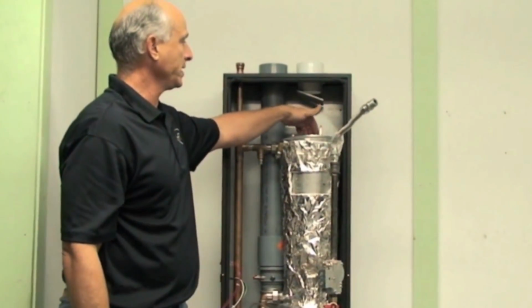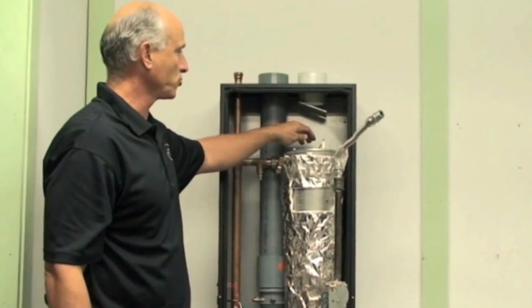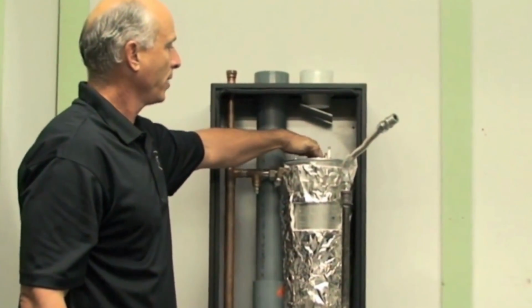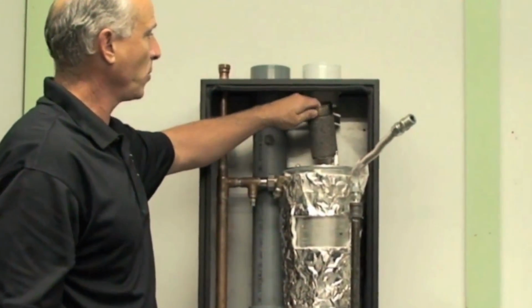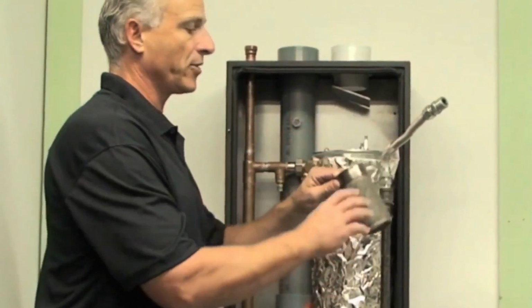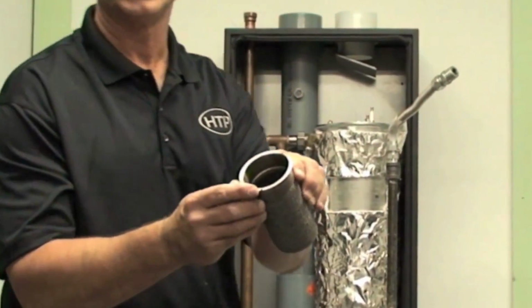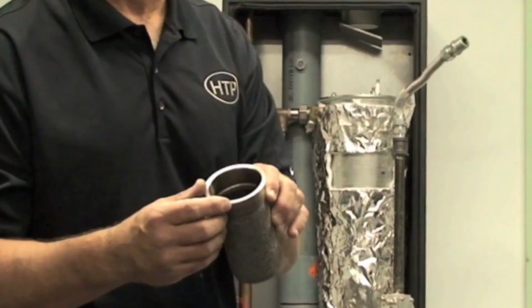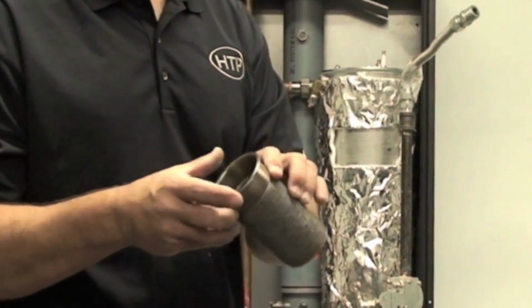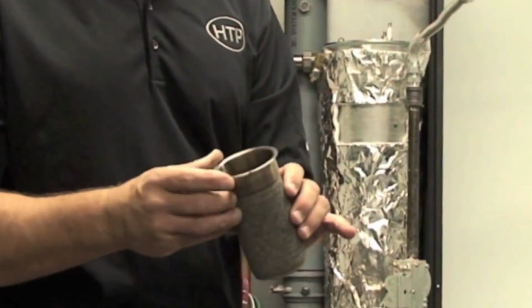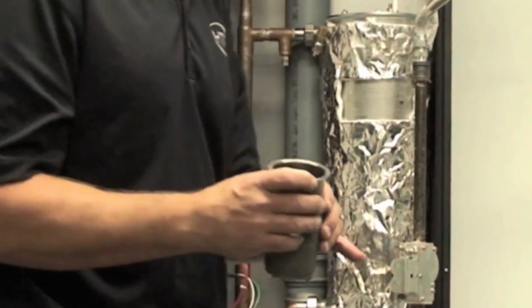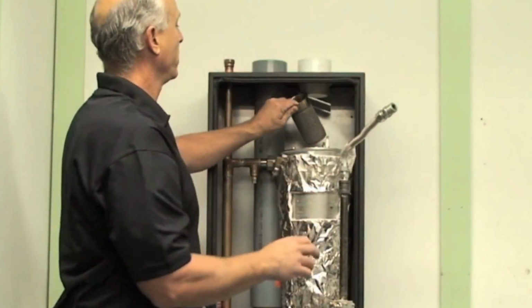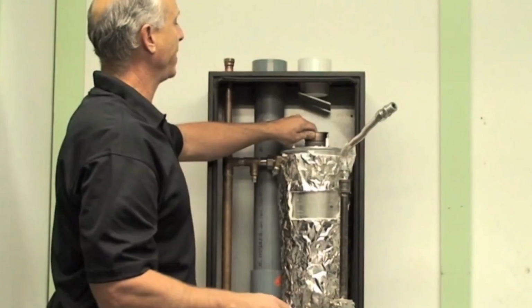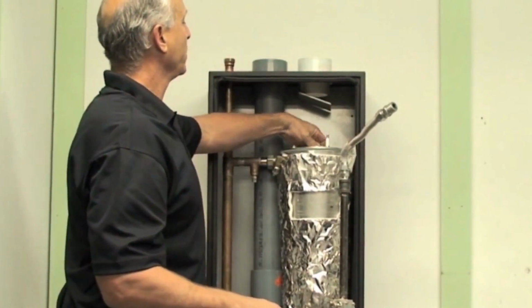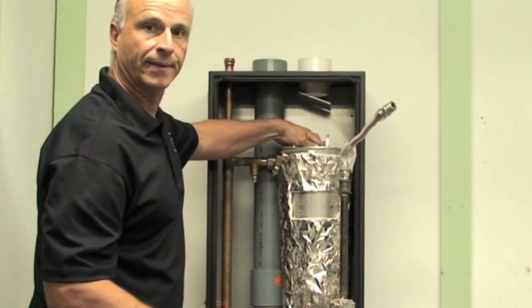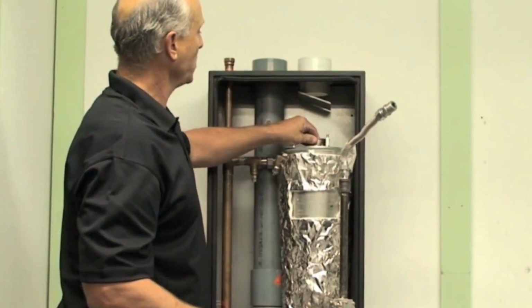Burner's real easy to take out. We constructed the boiler so the burner would clear the top of the boiler. So in order to take it out, you'll notice there's a little V-block. There's a little V-block here, and that's for alignment. So if you ever take the burner out and need to put it back in, make sure it goes into this V-block, which is located right here, and there's a recess in there, which will make it seat. You'll feel it, and you just lock it in. Okay, so that's the burner.